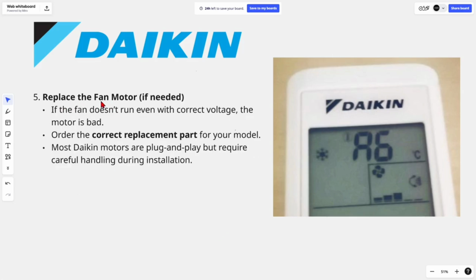Step 5, replace the fan motor if needed. If the fan doesn't run even with correct voltage, the motor is bad. Order the correct replacement part for your model. Most Daikin motors are plug and play but require careful handling during installation.